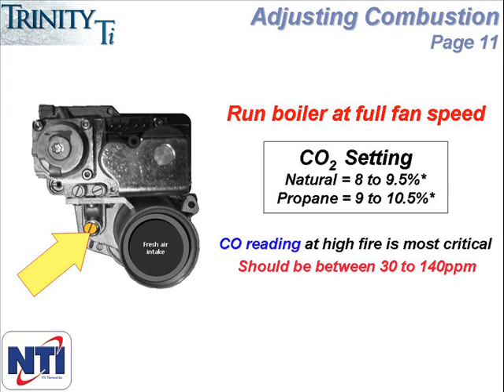Once the CO2 has been set at the appropriate level — either 9% for natural gas or 10% for propane — you then need to check the CO reading while still at high fire. This reading is actually the most important reading you'll take for the safe operation of the boiler.